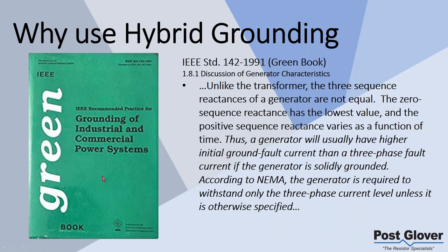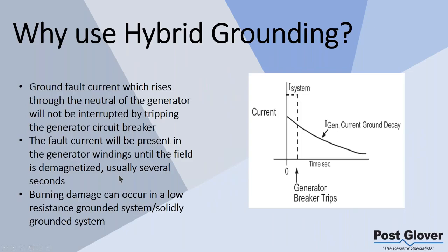We already have a low resistance ground system for our generator. The problem is, and I mentioned it already, the first published victim of this that we know of was a fairly large pulp paper plant. We don't need to go into details of who it is, but basically they had a low resistance ground system on cogen systems, a very popular design to have, with generators as well. But they had a fault. It turned out to be inside the generator, and the damage that occurred was alarming to them. It was a lot more than they were expecting, based on what usually happens in a low resistance ground system.